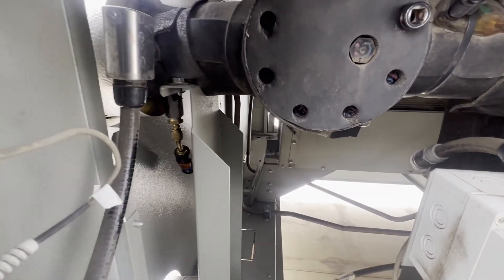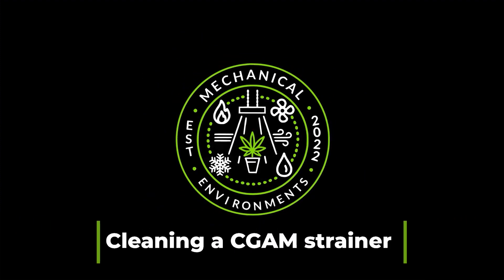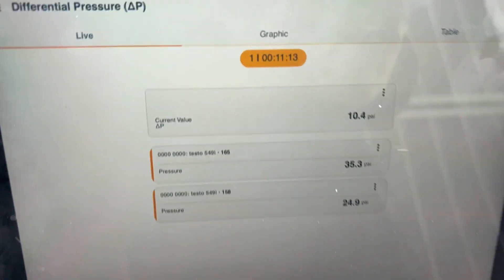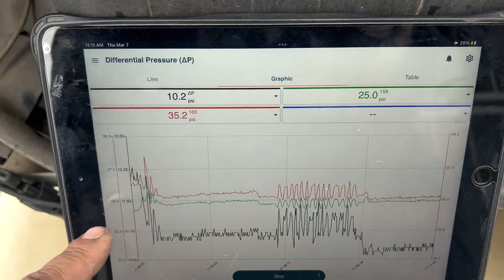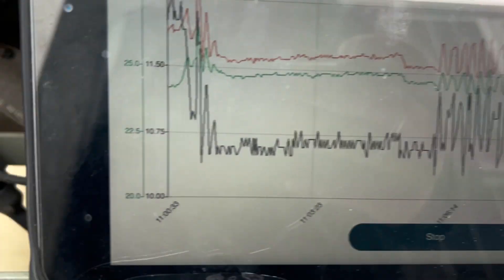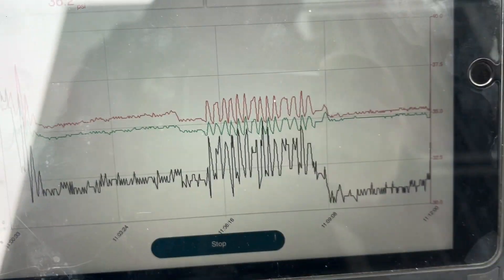This needs cleaning. Over the course of 11 minutes, we've gone all over the place in pressure, still maintaining 10 on our pressure drop, as high as 13 there at the beginning.